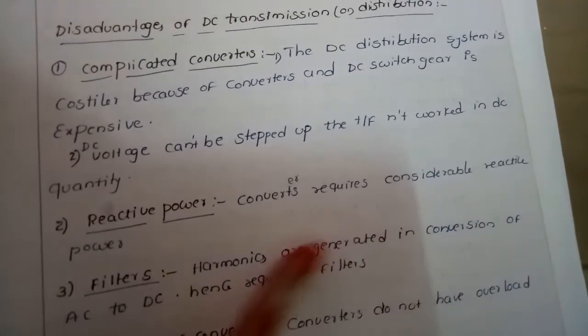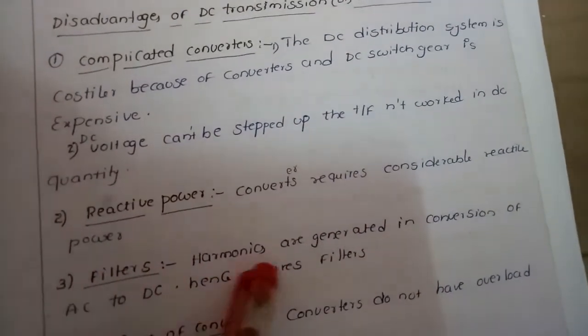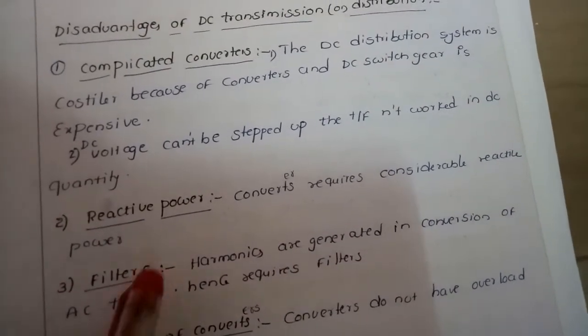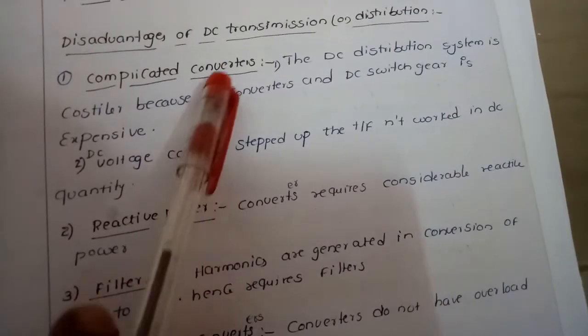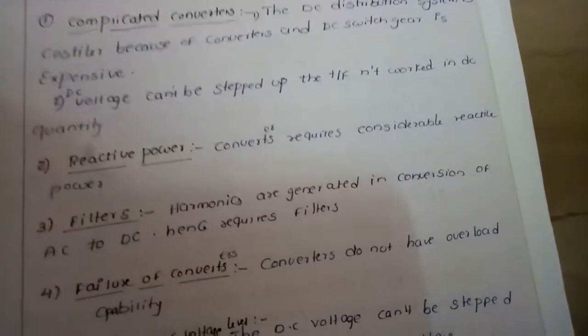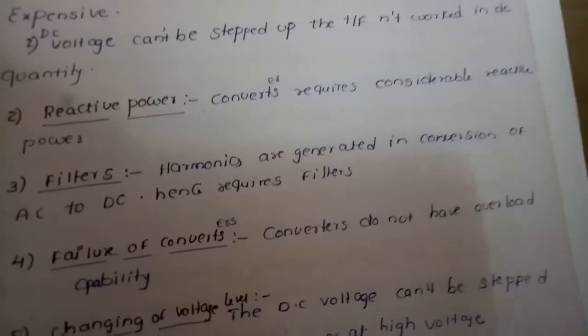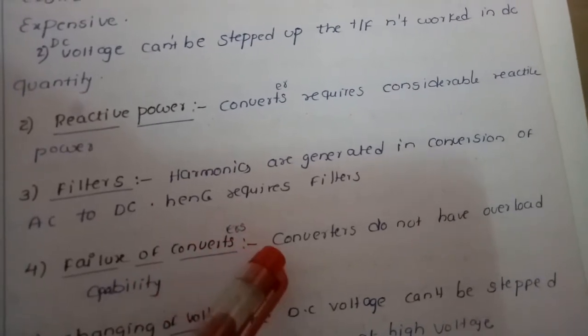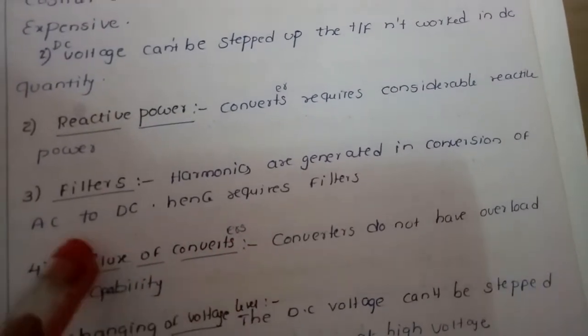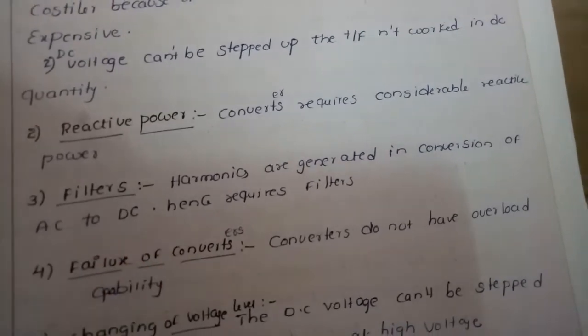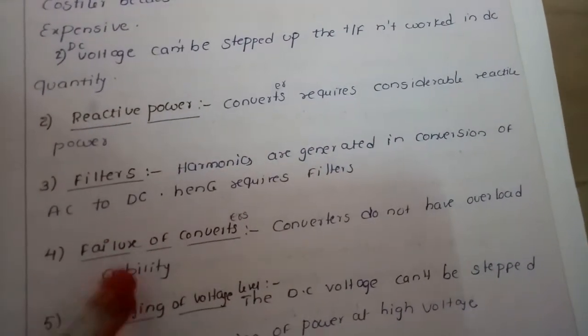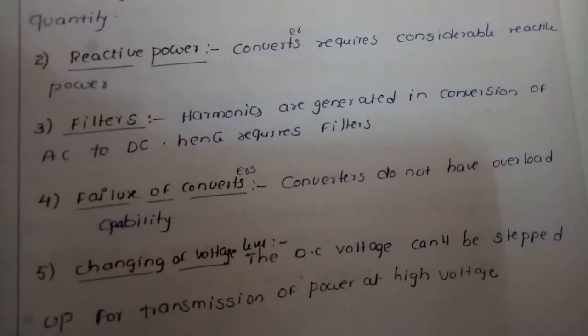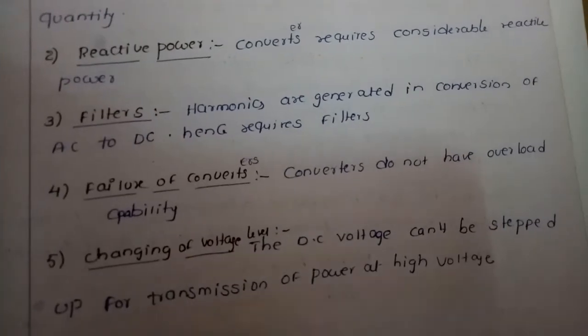Further disadvantages of DC transmission include the need for considerable reactive power and harmonic filters, which are costly. Converters do not have overload capability and failures may be more frequent. Change of voltage level is also not easily possible in DC transmission.